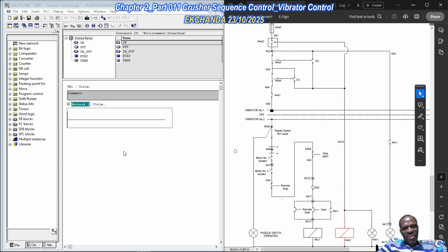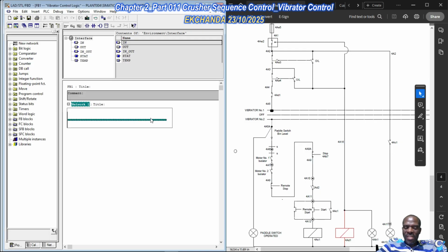So because of the way the protection inputs were being validated, we can modify this so we won't even bother with latching these protection states. Why? Because when these signals were being passed to the PLC and the inputs were being validated, just there, to normalize the system, we needed to reset those inputs.